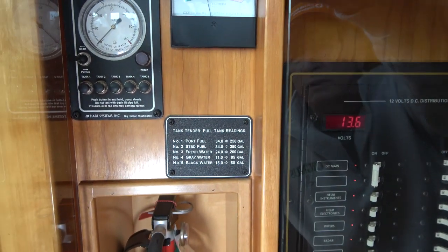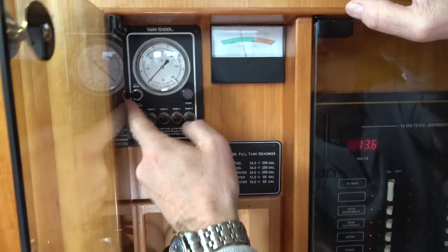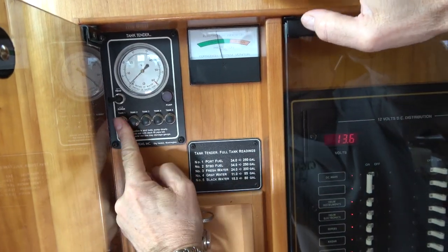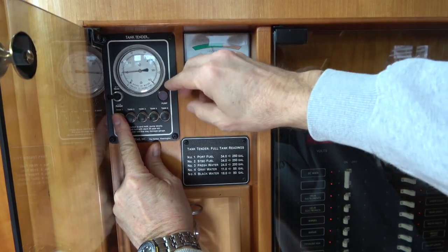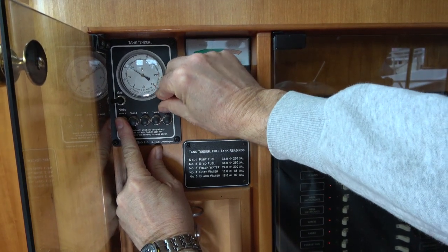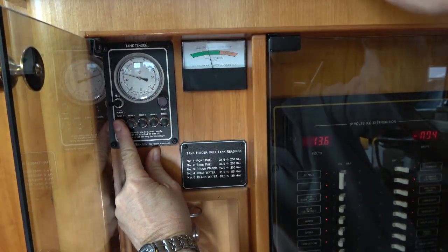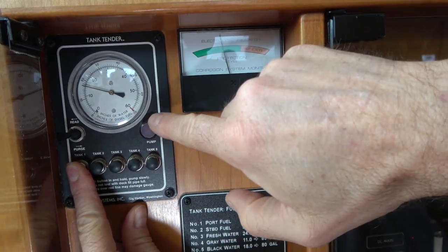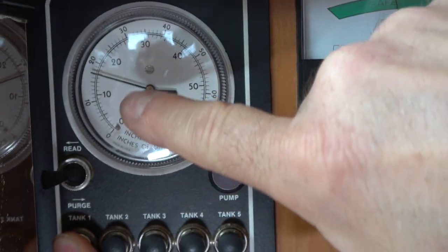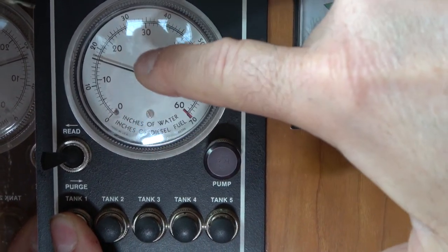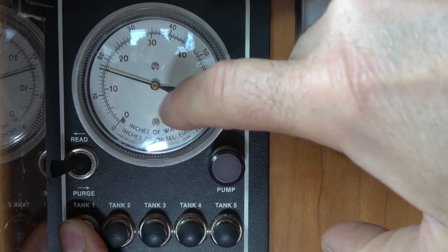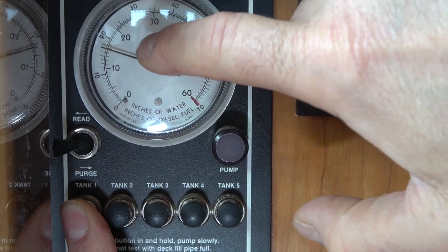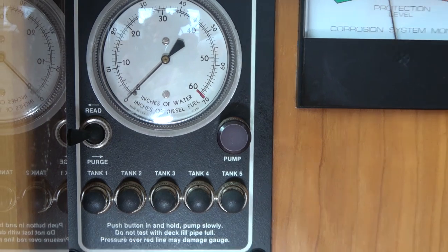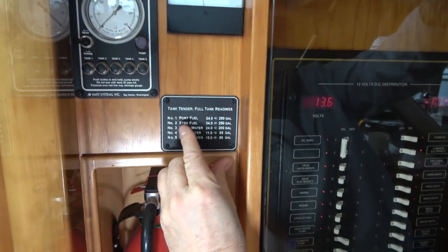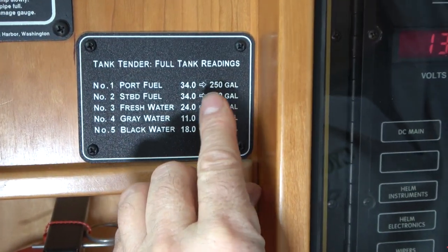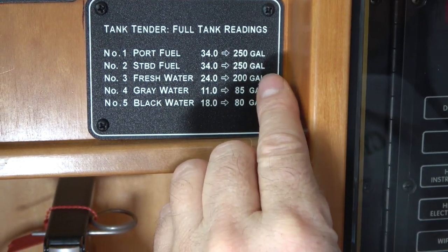The way it works is, if it's in the read position, you can hold the button in. This is for the port fuel, and you pump this slowly — right now it's reading about 17 inches of diesel fuel. The outer scale is diesel, the inner scale is water, showing about 17 inches of diesel, and according to this reading scale, 34 inches is full, which is 250 gallons.